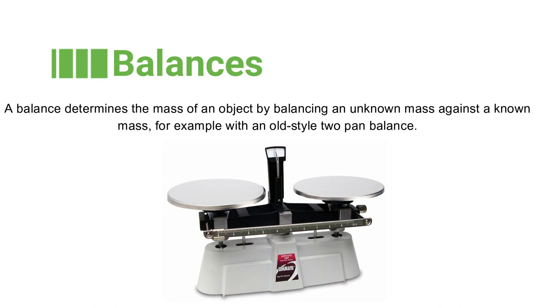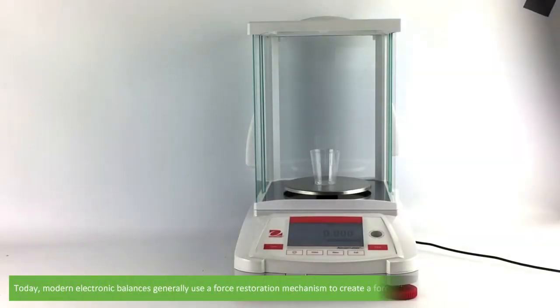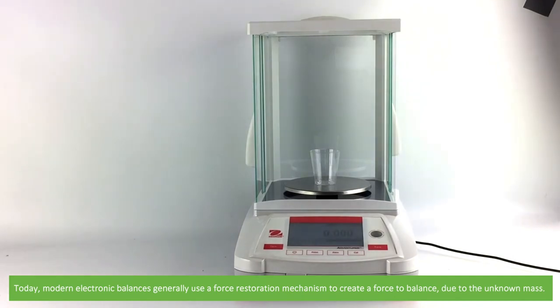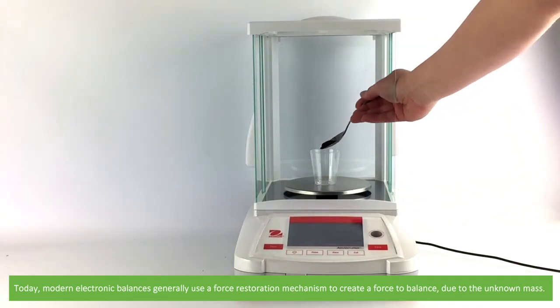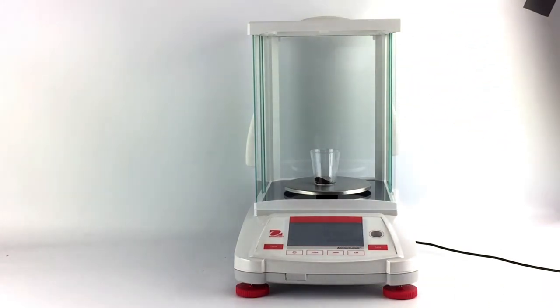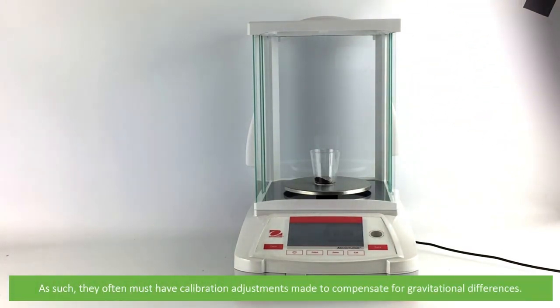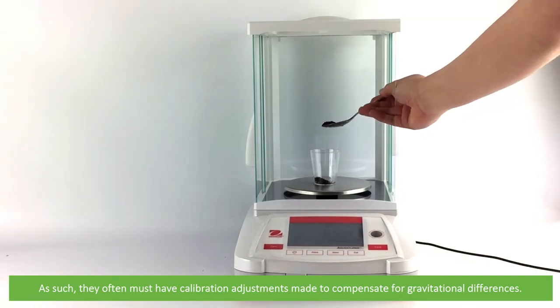A balance determines the mass of an object by balancing an unknown mass against a known mass, for example with an older style two-pan balance. Today, modern electronic balances generally use a force restoration mechanism to create a force to balance due to the unknown mass. As such, they often must have calibration adjustments made to compensate for gravitational differences.